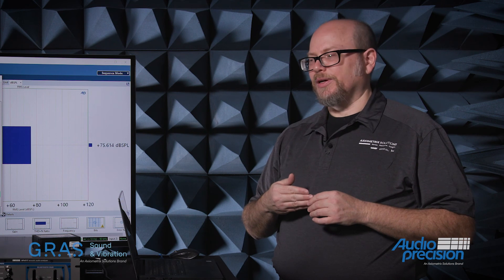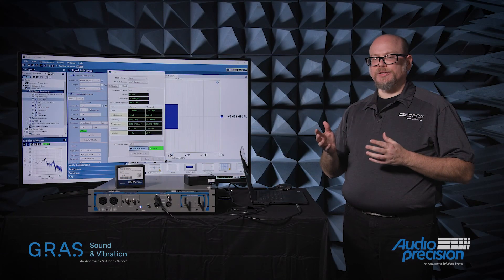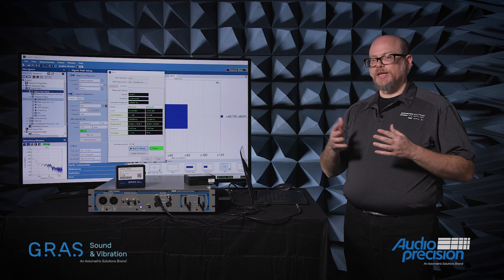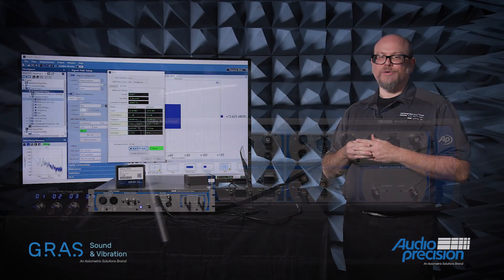SysCheck 2 is supported in Audio Precision's version 7 of our APX500 software, and it's supported using any of our analyzers with a CCP, or Constant Current Power Measurement, microphone interface. That includes the APX1701, the APX517, or any of our other analyzers when combined with a 1701, or one of the newer GRAS Type 12 BA, BB, or BC microphone power supplies.